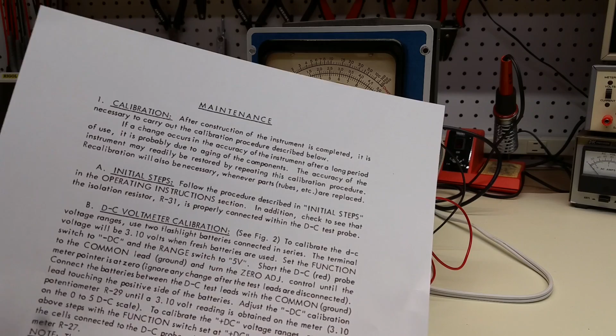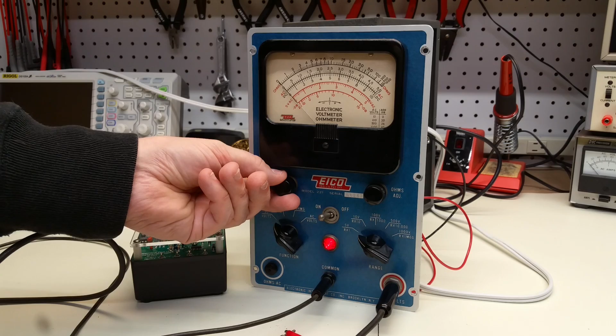All right, so the first thing it says is to set this to negative DC volts and to short out the common probe and the sensing probe, and to set the zero adjust to 0. And so there we go, just to show that this pot is working and functional. When I adjust it, I get deflection over a very substantial part of the meter.